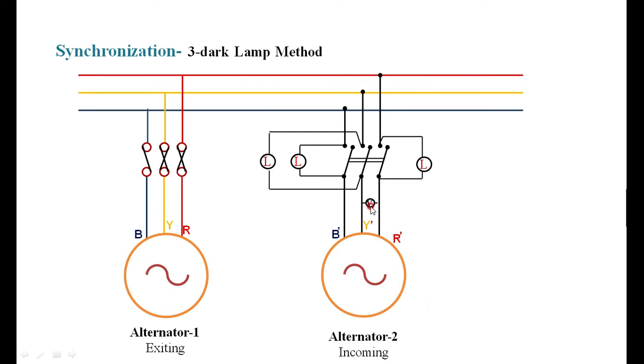To summarize: adjust the field so that the voltage matches the bus bar voltage, then check the phase sequence. The lamps should be going dark and bright simultaneously — if they are blinking at the same time, you can conclude that the phase sequence matches the bus bar phase sequence.